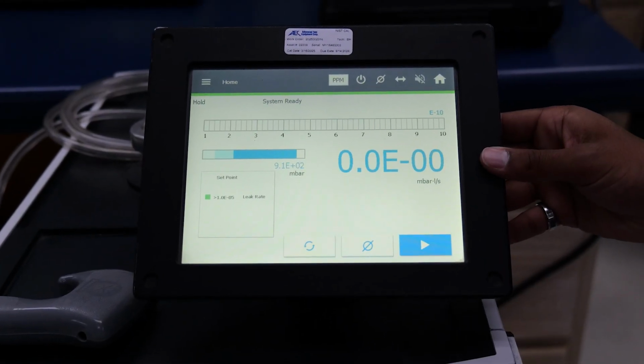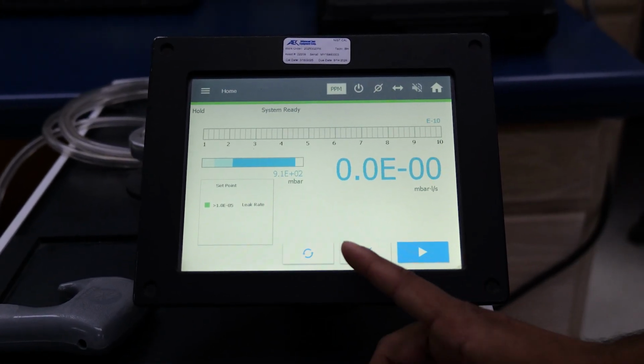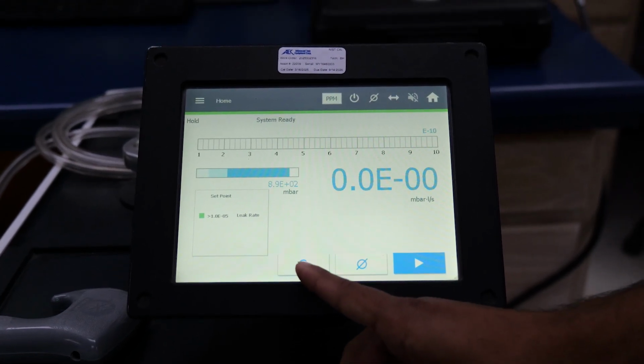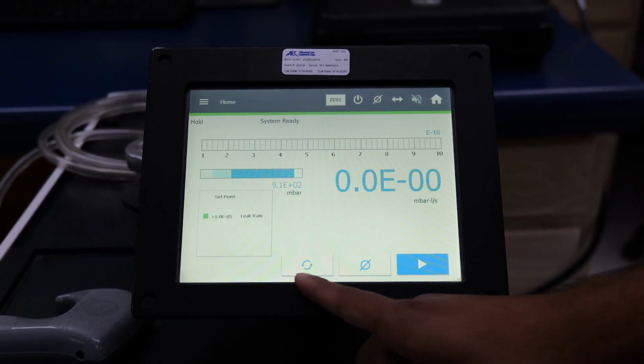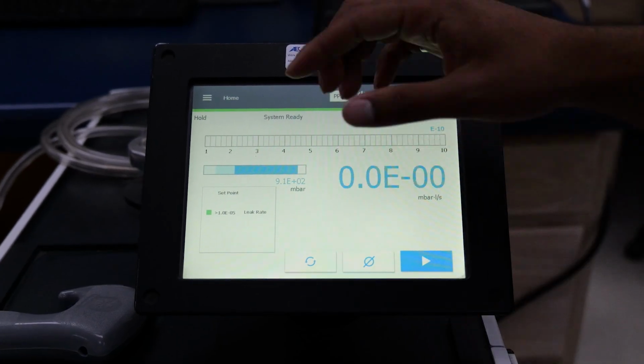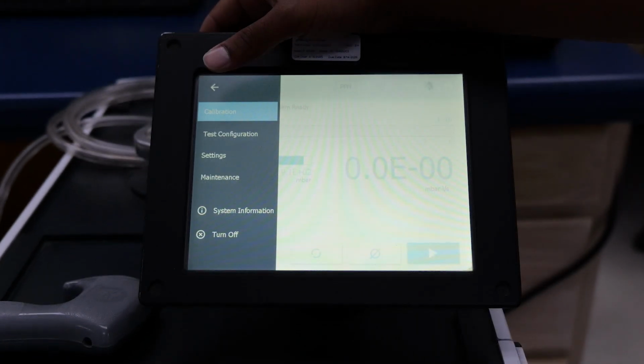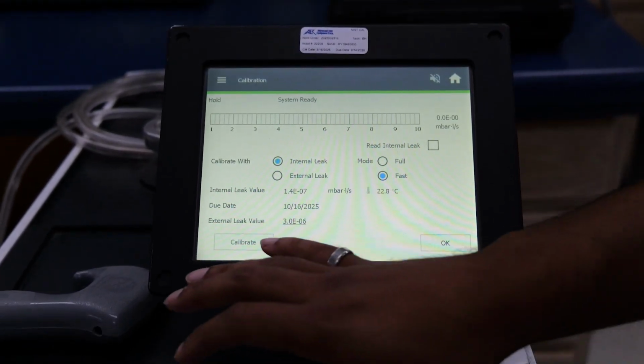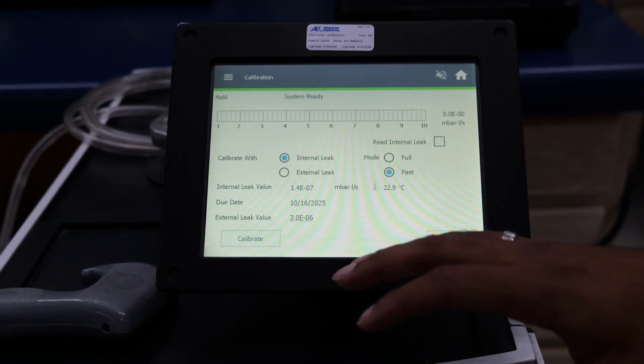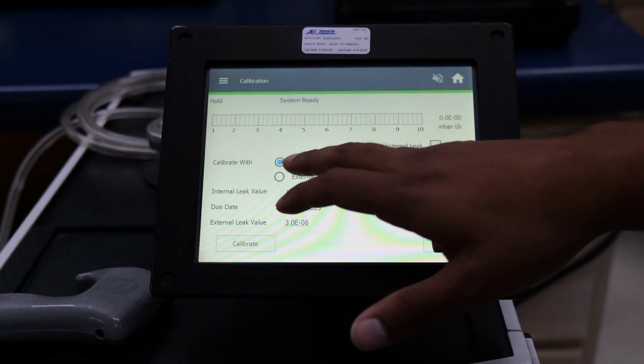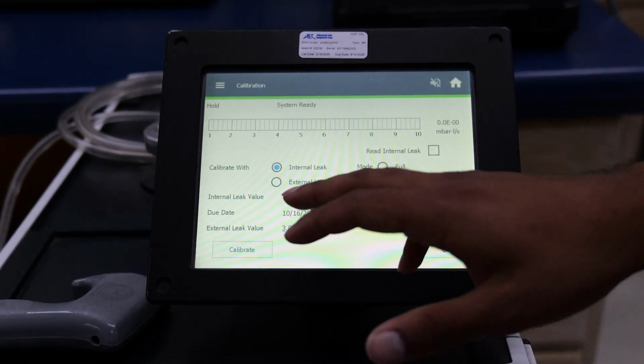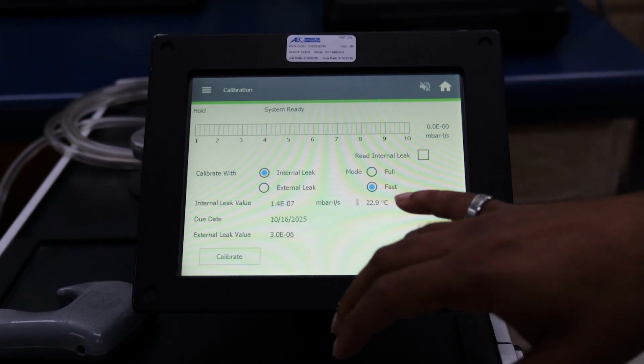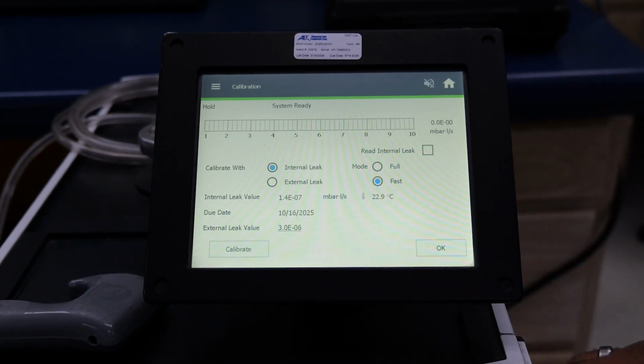Looking here at our front panel screen, we can see that we have our zero button and a vent button. These are pretty standard in all helium leak detectors. We can go over here and see we have a calibration menu, and here you can calibrate the unit to make sure it stabilizes and does accurate readings. We can do it with the internal leak or an external leak. There's an internal leak installed in the unit, so it's pretty easy to just turn the unit on and hit calibrate and everything is good to go.